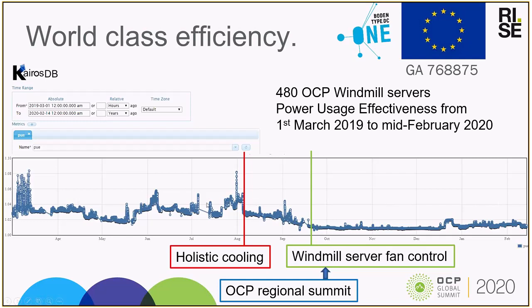This starts back in February or March last year, where we started to run some experiments. You can see that the PUE fluctuates between 1.02 and 1.08 at the beginning here. There is no centralized UPS, which is why the PUE can go down as low as 1.02. Then we introduced this concept of holistic cooling control around August last year. This is where we generated the ability to communicate information from the IT system to the ventilators and the coolers, and this enabled us, by process control, to drop the PUE a little bit and get that under control.